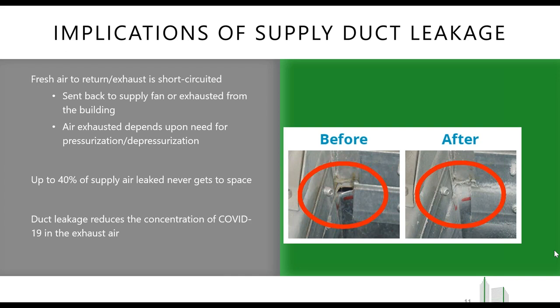What that short circuiting also causes is an increase in fan energy. This means your fan is constantly working harder, and it's also bringing in more outside air to try to meet those demands of the space. But if you seal up the ductwork, you're not only going to increase the indoor air quality of the building, you're also going to solve a lot of those energy losses, because you're going to stop that short circuiting. What it says at the bottom is that duct leakage reduces the concentration of COVID in the exhaust air, which is exactly what I showed you before.